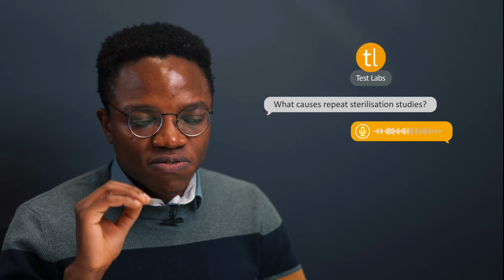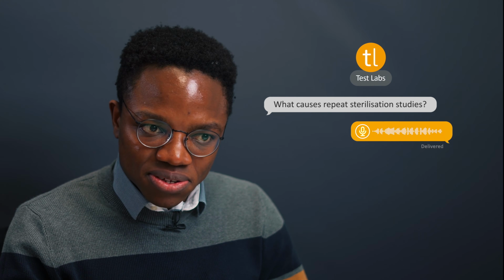The key point is to assess your device, see how compatible it is with your sterilization process, and then keep that in mind before you perform the testing. The point of testing is to see what needs to change. So a failure is never the end of the world. In fact, a failure is good because now you know exactly what needs to change with your device, and the regulators will love to see that you did do your due diligence, you did test properly, and you did implement the corrective actions to make sure your device is fit for purpose and safe for the patient to use.